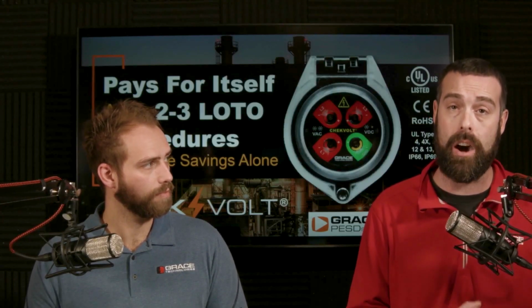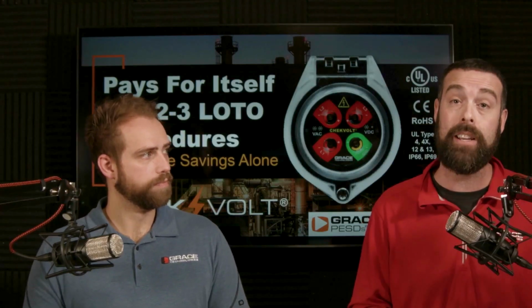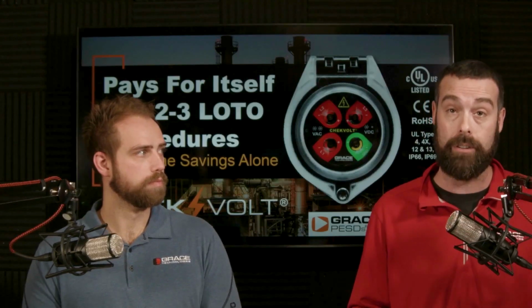I want to add a point that holds a lot of weight. As mentioned, these are externally mounted devices acting as an extension of your point of work. We're not changing your lockout tagout procedure - we're just allowing you to do it in a much safer and efficient way by keeping the enclosure door closed and reducing the overall incident energy or arc potential of that interaction. You still have the ability to walk up with your trusty voltmeter or multimeter, test each phase conductor, phase to phase to ground, to ensure you've truly isolated the power.